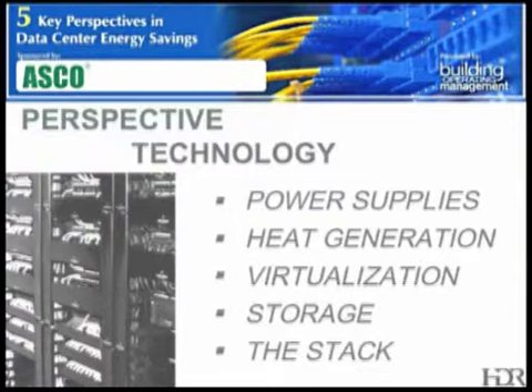Then we take a look at how that scales down to the heating and the cooling in the data center. Your heat generation goes down, cooling requirements go down, and that has to be teamed with the facilities group. Depending on the set points and the delta T's in the data center, as these virtualization strategies reduce the amount of IT infrastructure in the data center, the data center is just going to get cooler and cooler. Then you can run into a challenge with the efficiency of your cooling units.